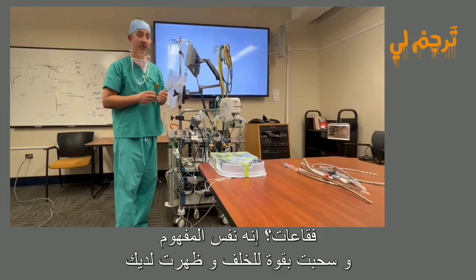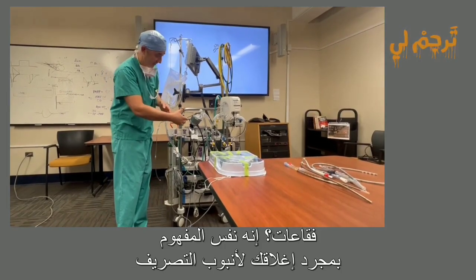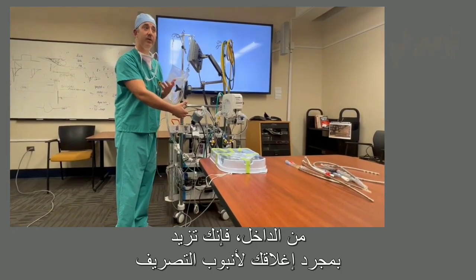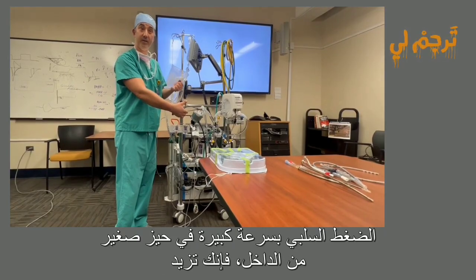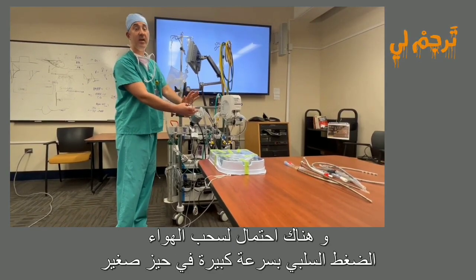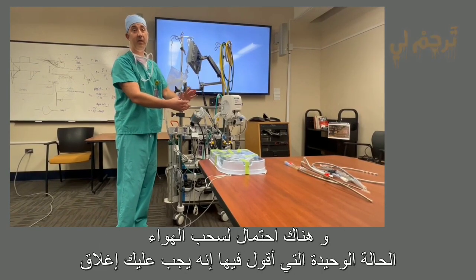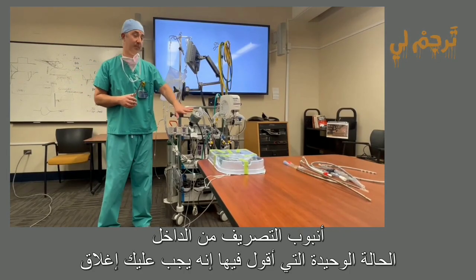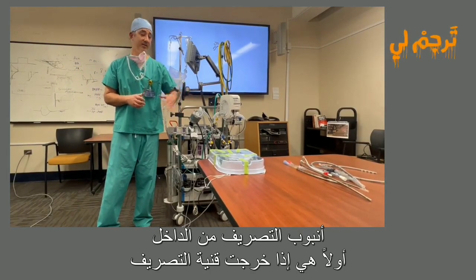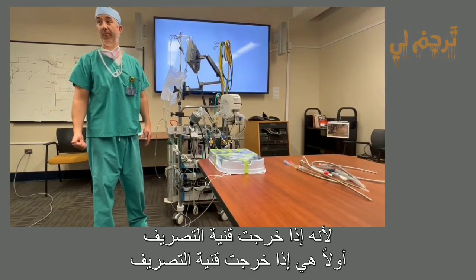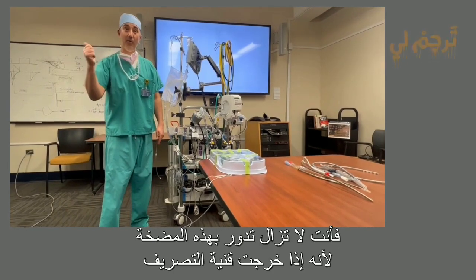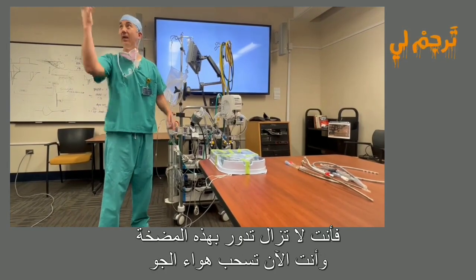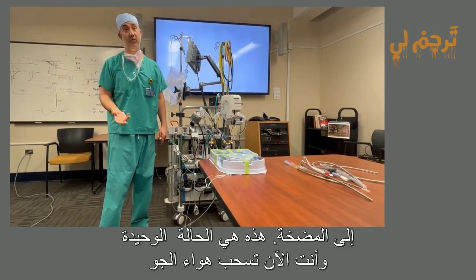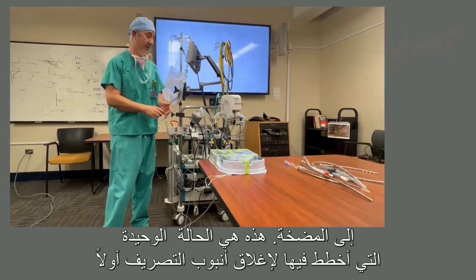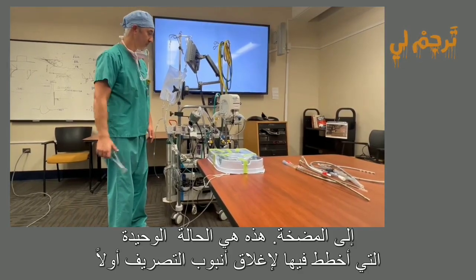It's the same concept. By clamping that drain side, you're increasing that negative pressure very quickly in a small volume of space, and you have the possibility of pulling air. The only time I would ever say you would clamp the drain side first is if the drainage cannula came out. Because if the drainage cannula came out, you're still spinning with this pump, and now you're sucking atmospheric air into your pump. That's the only time I would ever clamp the drain side first.